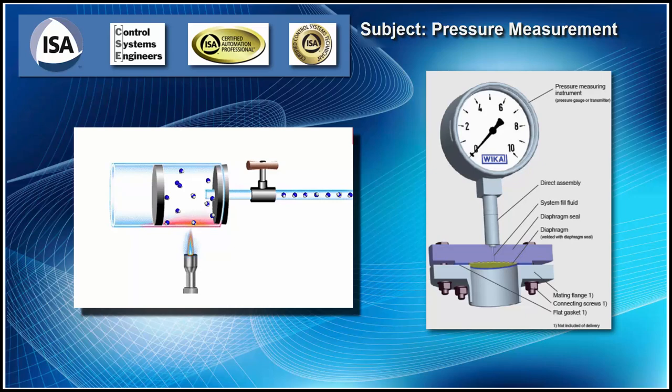Okay, so if we look at this pressure gauge here on the right, we'll see down at the bottom, it has a diaphragm, and they'll call this a seal or a diaphragm. And this seal, again, your molecules are just pounding against it. And basically, this is filled with typically a silicon fill or oil fill going up to the bourdon tube in the pressure gauge. And this is a mechanical amplifier or mechanical repeater. It just repeats the pressure to the gauge so we can read this gauge.